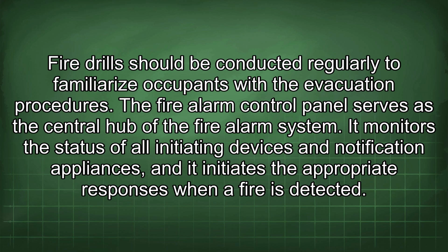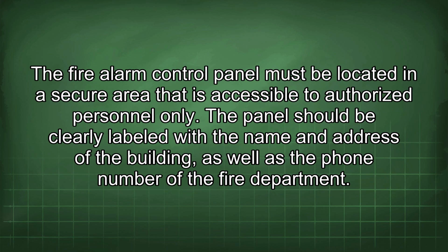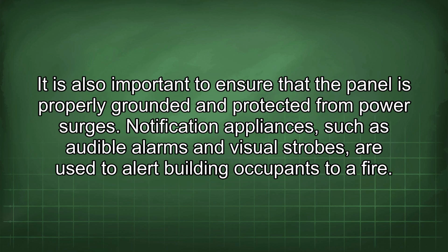The fire alarm control panel serves as the central hub of the fire alarm system. It monitors the status of all initiating devices and notification appliances, and it initiates the appropriate responses when a fire is detected. The fire alarm control panel must be located in a secure area that is accessible to authorized personnel only. The panel should be clearly labeled with the name and address of the building, as well as the phone number of the fire department. It is also important to ensure that the panel is properly grounded and protected from power surges.